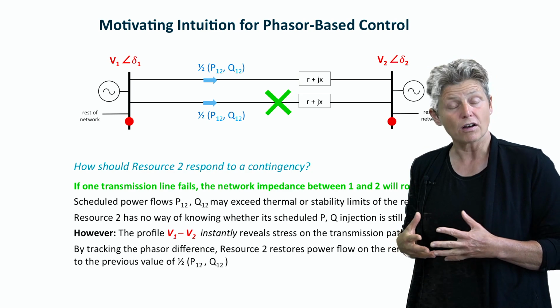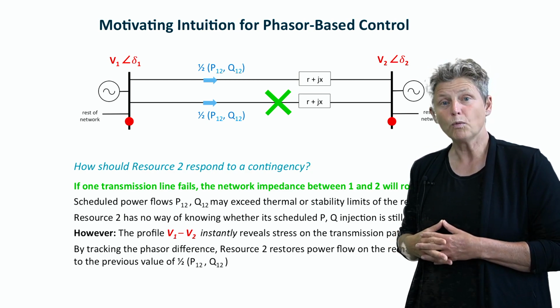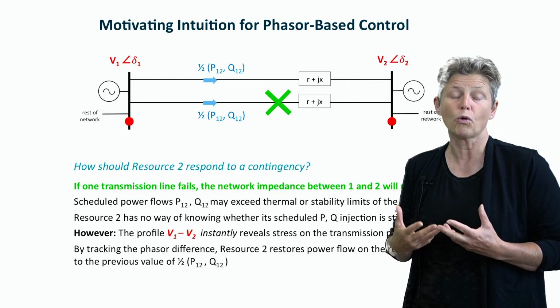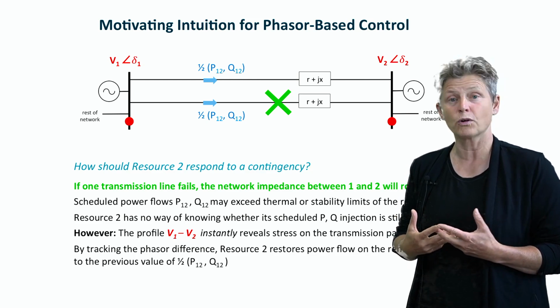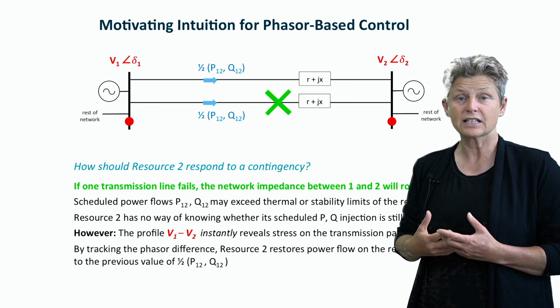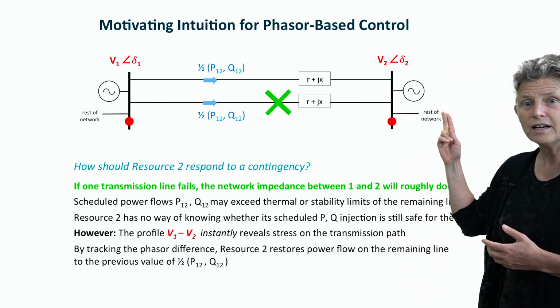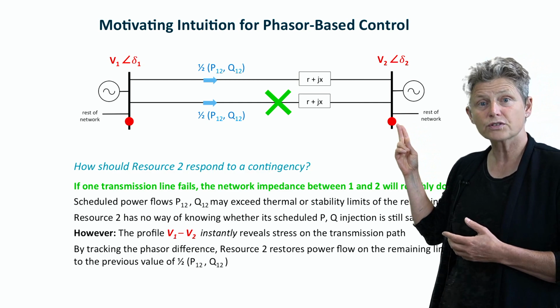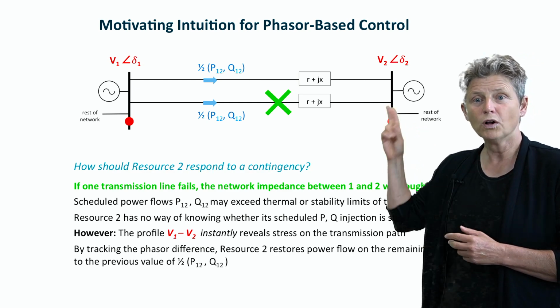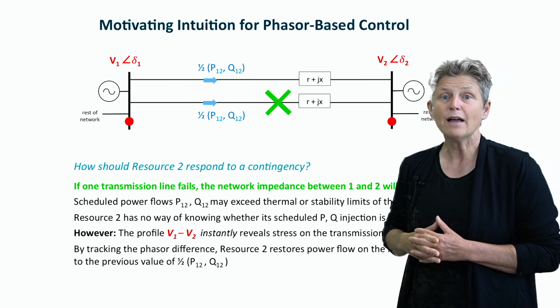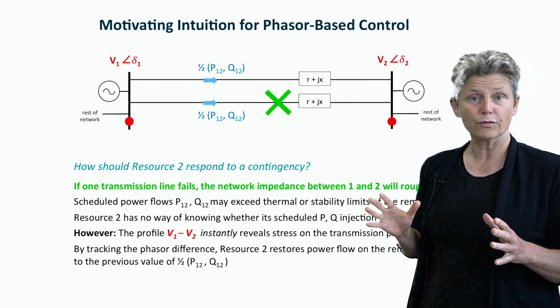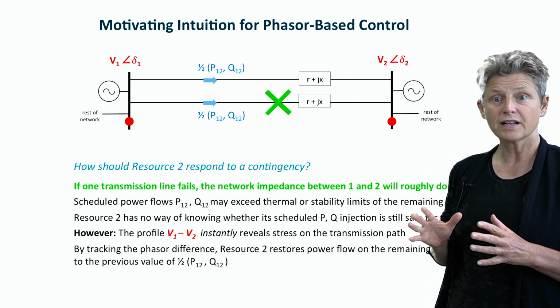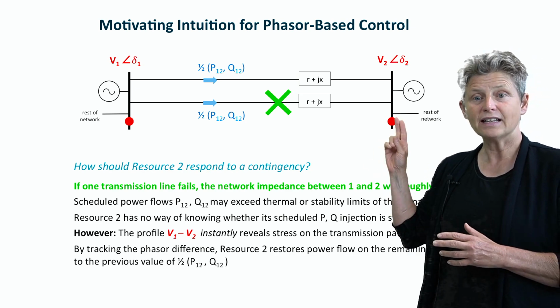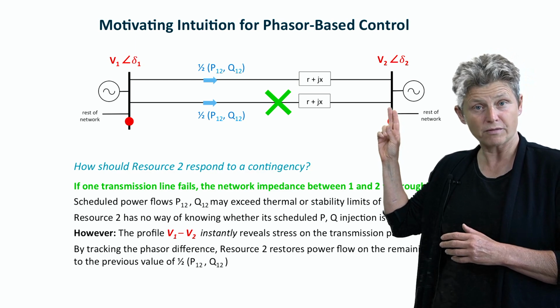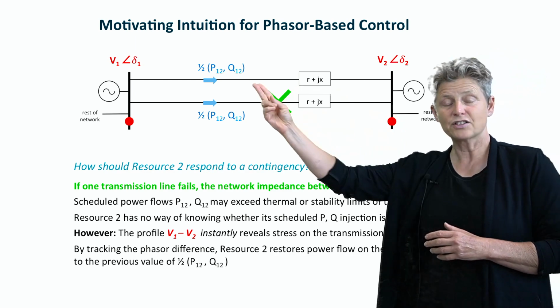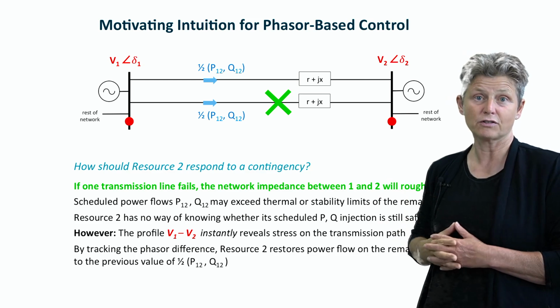it may be operating on an emergency rating. And so we want to get it back, restore it to the original operating condition, or at least to a safe condition, as quickly as possible. So with phasor-based control, the resource at bus 2 will observe the step change, and without having to wait for any further information or instruction, it will know that it needs to step up its generation or step down its load as this phasor difference suddenly increases.